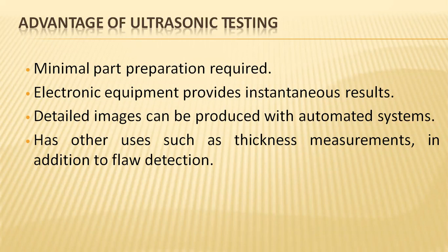Even image capturing is also possible, with automated control systems provided as programmed devices within the control system itself. So the images will be captured up to the depth of penetration the sound waves reach, and the identified cracks or defects and their dimensions will also be captured in the form of an image for good accuracy signal formation.